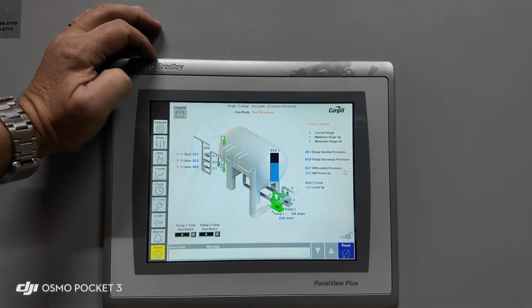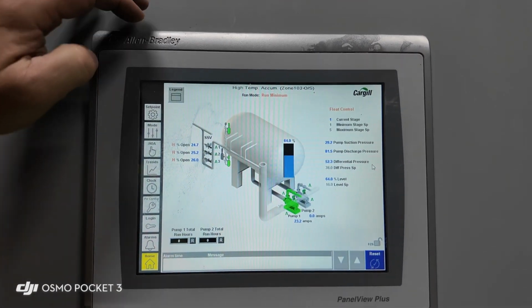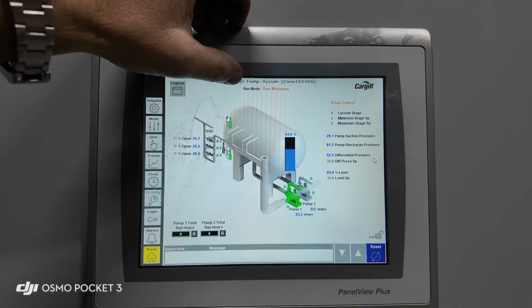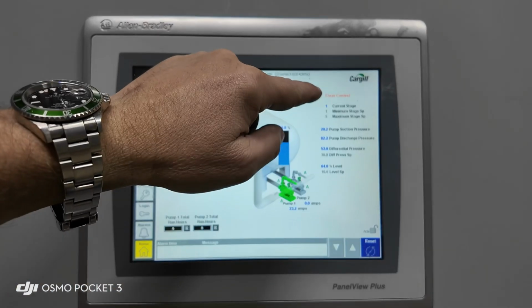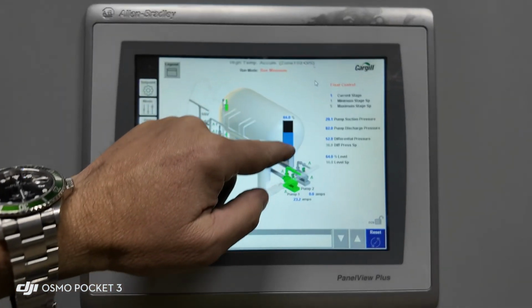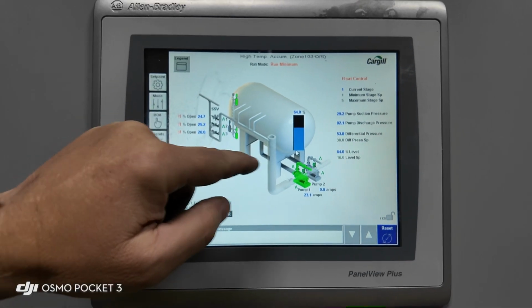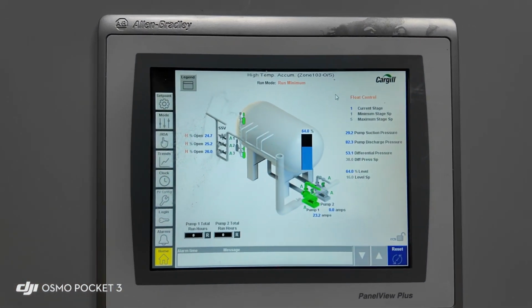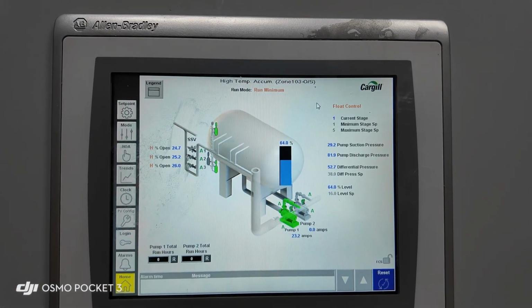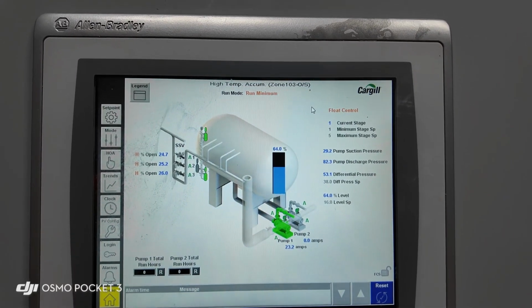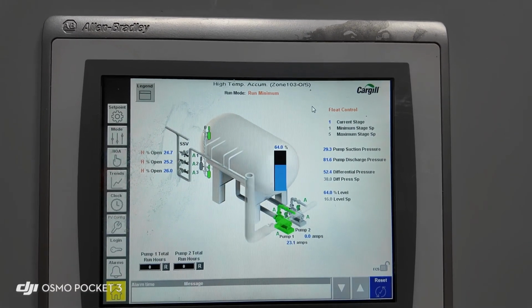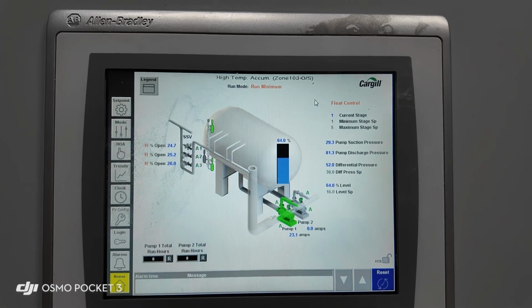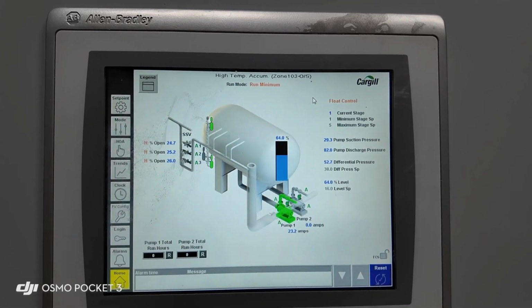On the main screen, we have the pertinent information on this panel. What its zone is, what its run mode is, what type of control it's in, whether it's in vessel level control or vessel float control. It's currently in float control. The current stage it's in, the minimum stage set point, maximum stage set point, pump suction pressure, pump discharge pressure, pump differential pressure, and the differential pressure set point.